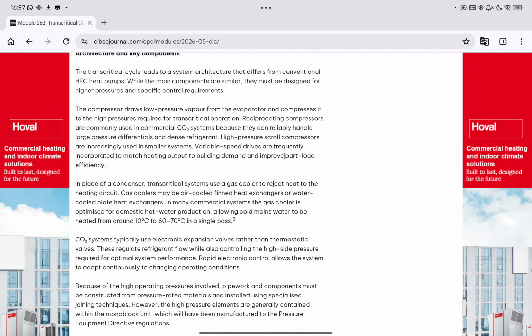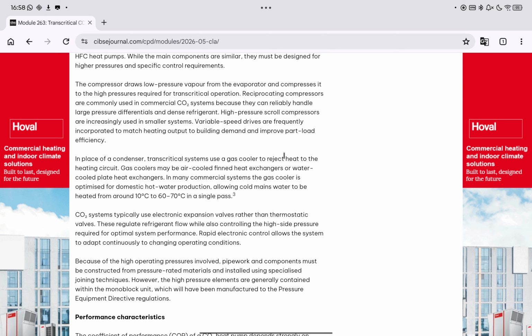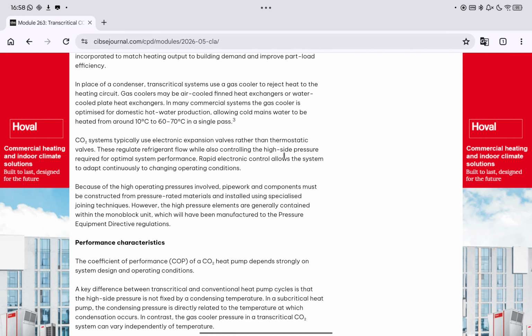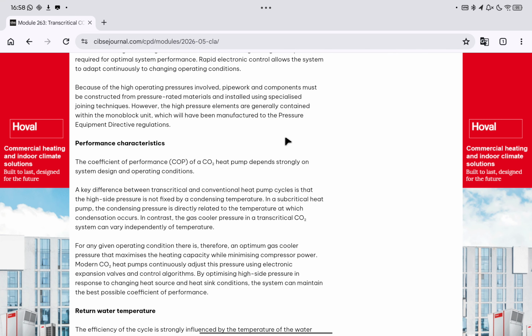CO2 systems typically use electronic expansion valves rather than thermostatic valves. These regulate refrigerant flow while also controlling the high side pressure requirement for optimal system performance. Rapid electronic control allows the system to adapt continuously to changing operating conditions. Because of the high operating pressures involved, pipework and components must be constructed from pressure-rated materials and installed using specialized jointing techniques. However, the high-pressure elements are generally contained within the monoblock unit, which will have been manufactured to the Pressure Equipment Directive regulations.